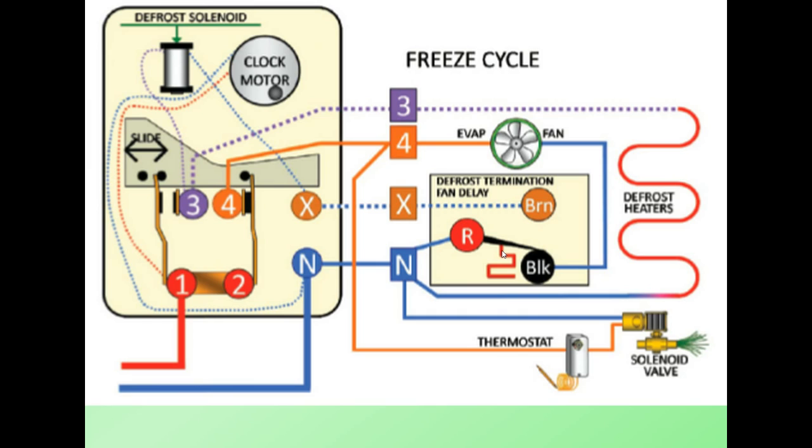Whenever you see this device, if the temperature increases it pushes it up in this direction and will move this contact back and forth depending on the temperature. We're going to break this down through every one of the loads and everything that's connected to the defrost clock, even if they're not operating in the freeze cycle. We're going to follow the paths to see what happens.